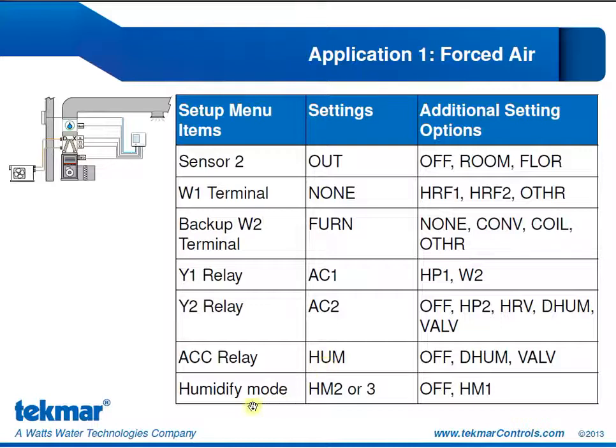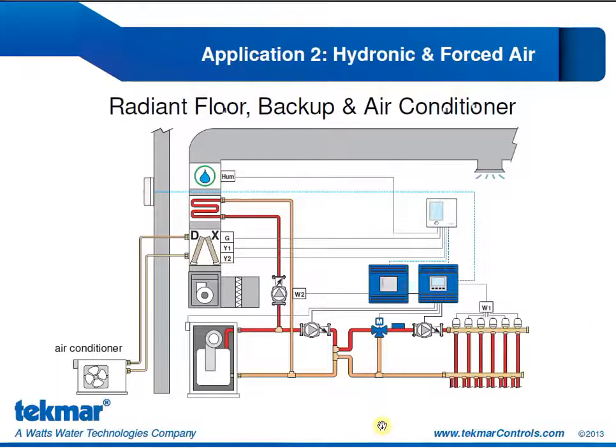Our Y1 and Y2 relays are the stages of air conditioner. Our accessory relay is controlling the humidifier, and because this humidifier is in the ductwork, it's going to be humidify mode 2 or 3. It is not a standalone humidifier.